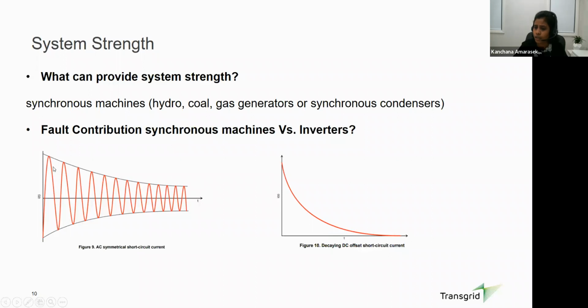So as you can see here, a synchronous machine has a very high short-term capacity. It can provide up to 5 to 6 times the rated current for a few cycles, and 2 times the rated current for up to a few seconds, and it decays faster, but this short-term overload capability is really helpful. But if we compare a synchronous generator to a similar sized inverter, usually they have a flat response. Sometimes they claim they have some contribution. Even if they do, compared to a synchronous generator it's quite small, and it's for a very short duration as well. So this is another key difference between synchronous machines and inverter-based generators.